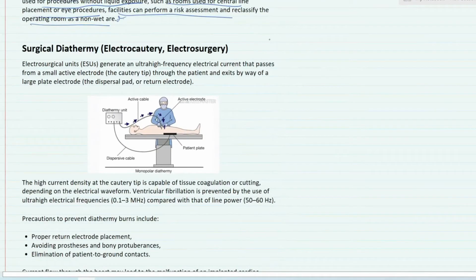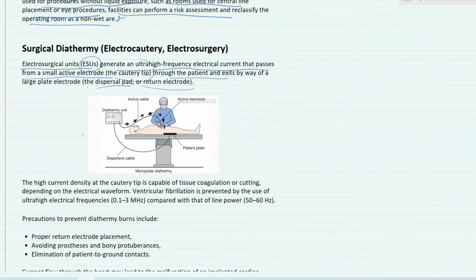Now talking about surgical diathermy. What is surgical diathermy? I think most of us have seen a surgical diathermy. Electrosurgical units, ESUs, generate an ultra high frequency electrical current that passes from a small active electrode, the cautery tip, through the patient and exits by way of a large plate electrode, the dispersal pad or the returning electrode. So this is a diathermy unit, and electrosurgical units generate ultra high frequency electrical current, which as we have discussed is an AC current. It is high frequency, right?